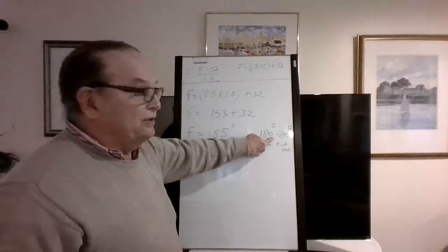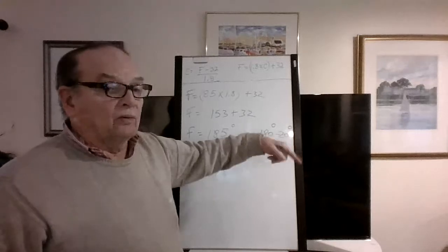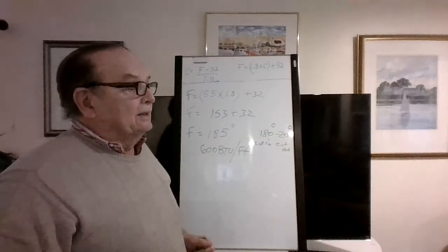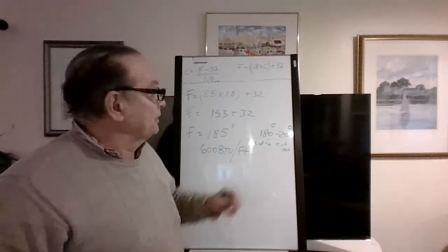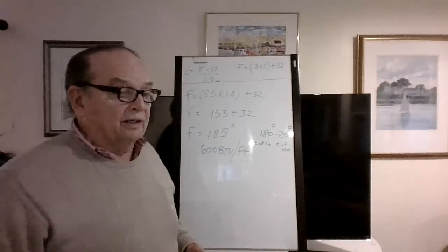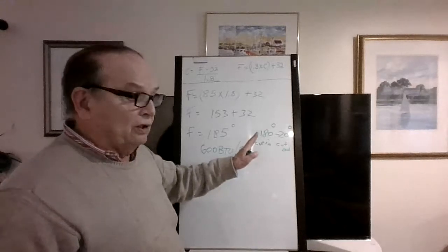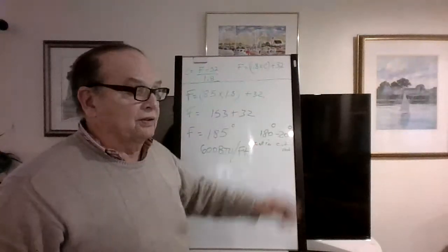Now, can you change this number? Yeah, some guys go like 190, 210. My advice is don't do that. Go with the 180, 200. If there's a problem or if they add a room or there's a screw up in the calculations, you always got a little cushion and you can adjust the temperature.